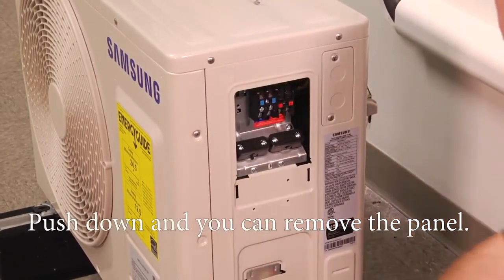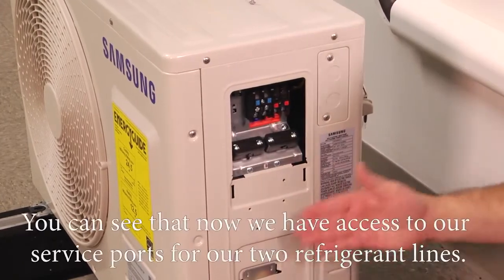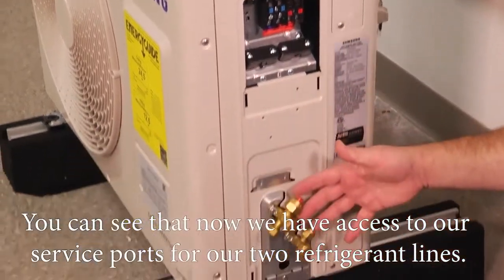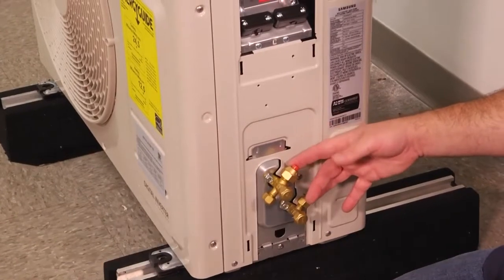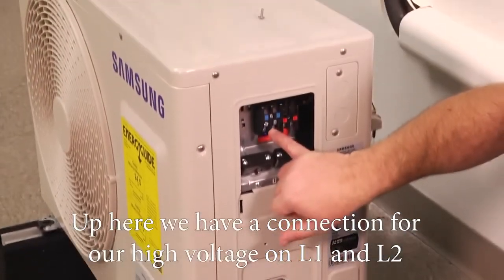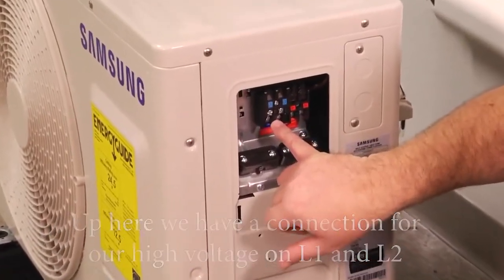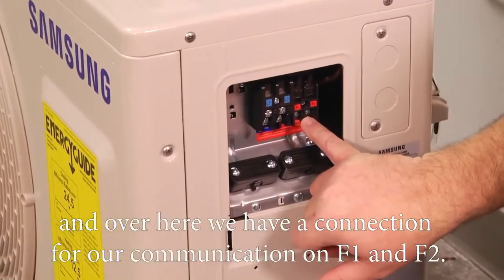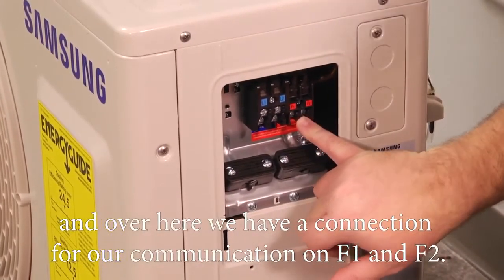Push down and you can remove the panel. And you can see that now we have access to our service ports for our 2 refrigerant lines. Up here we have a connection for our high voltage on L1 and L2. And over here we have a connection for our communication on F1 and F2.